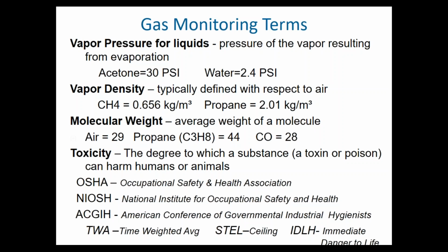And of course, coming out of an engine being hot, we all know hot air rises as well. So carbon monoxide probably should be detected at the ceiling. So that's how you can determine that molecular weight is a good way of determining where to place the sensors.